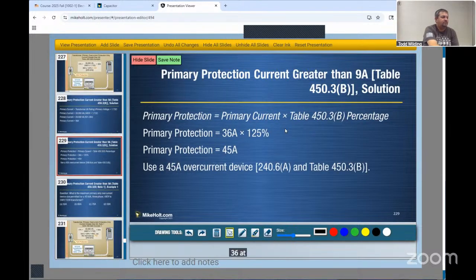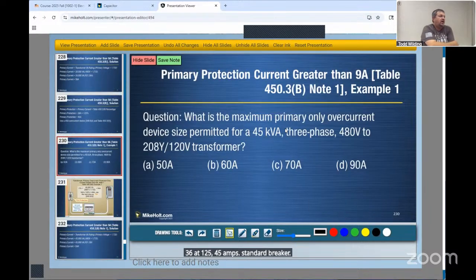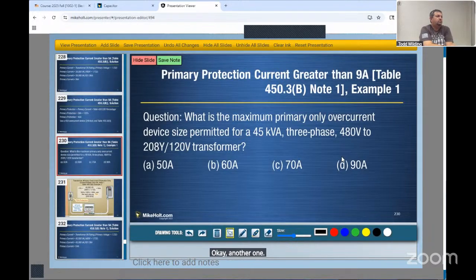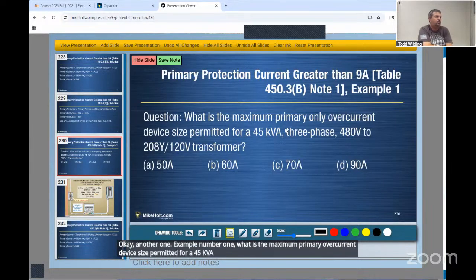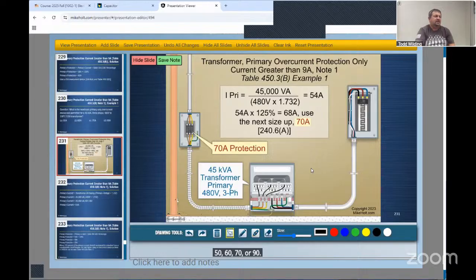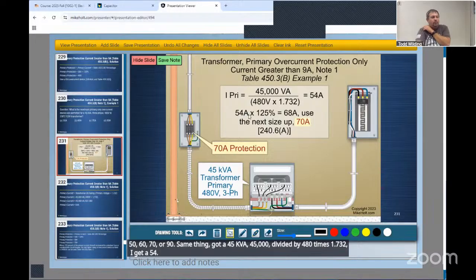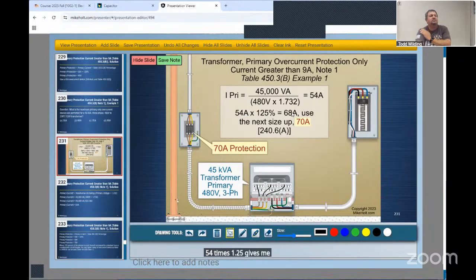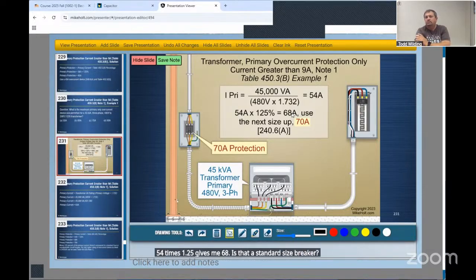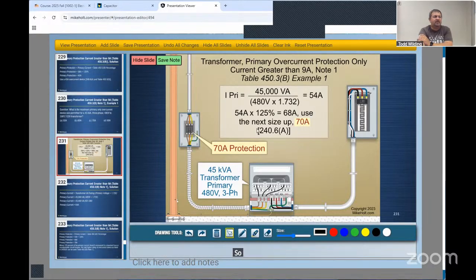36 at 125, 45 amps, standard breaker. Okay, another one. Example number one: what is the maximum primary overcurrent device size permitted for a 45 kVA three-phase 480 to 208/120: 50, 60, 70, or 90? Same thing, I've got a 45 kVA, 45,000 divided by 480 times 1.732, I get 54. 54 times 1.25 gives me 68. Is that a standard size breaker? No. What's it fall between? So it goes 60, 65, 70, right? So I can bump that up to a 70 amp protection right there.